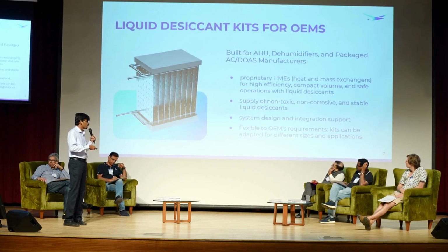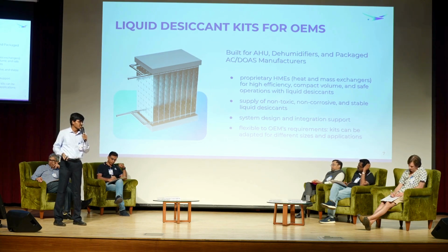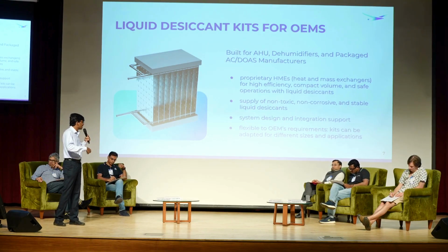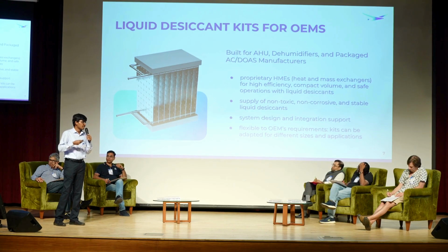We're also working on liquid desiccant kits that go into air handling units, so existing AC and AHU manufacturers can integrate them into their products and launch desiccant-based air conditioning products. The application isn't limited to industrial cooling and dehumidification; it's also applicable to commercial cooling, especially places using newer technologies like chilled beam-based systems, radiant cooling, and displacement ventilation.